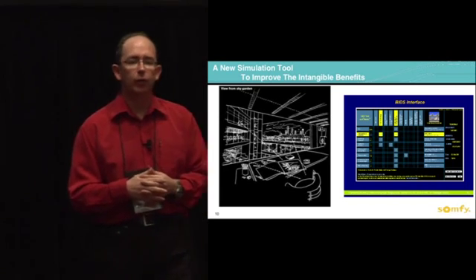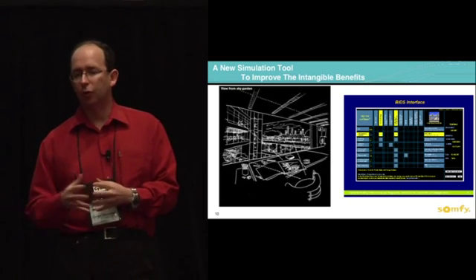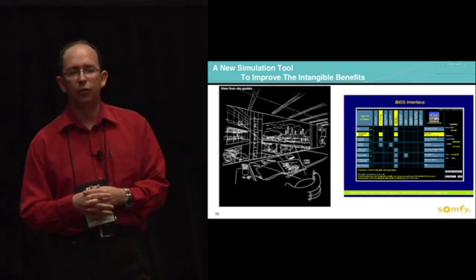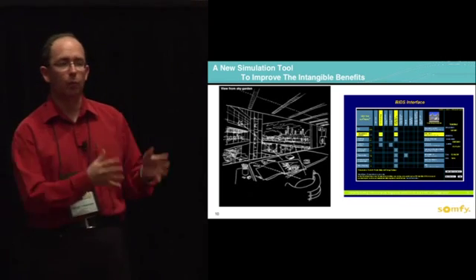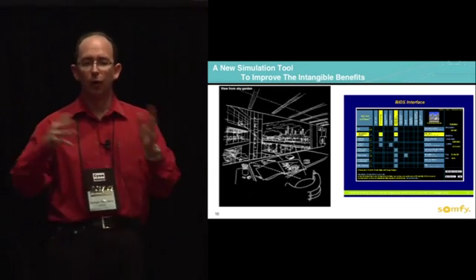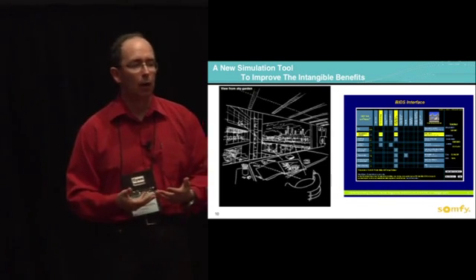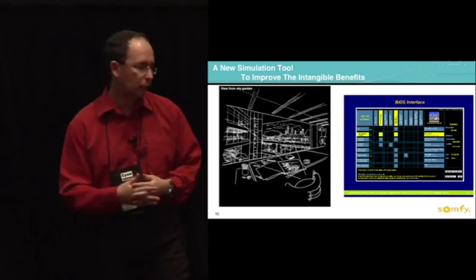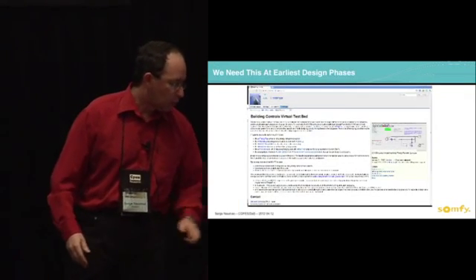And the second challenge is the building automation system itself, because they have sensors, because they have actuators. These sensors and actuators act just as filters. So the figures coming from the simulation are not used immediately by the system, and the system won't react immediately. And this also has to be taken into account if you want to make a dynamic passive solution simulation.